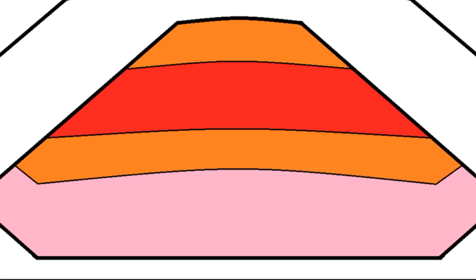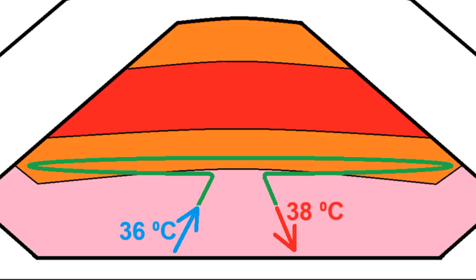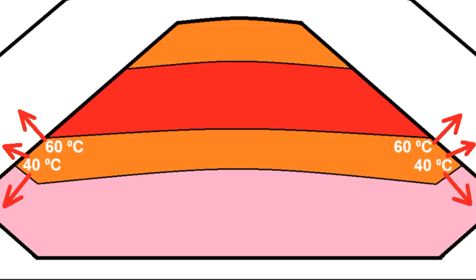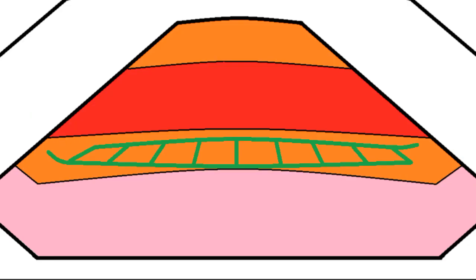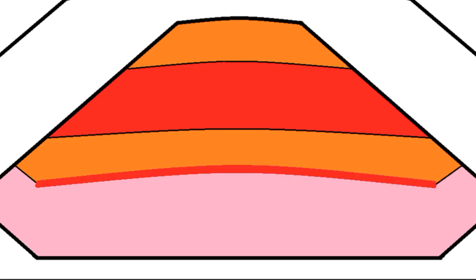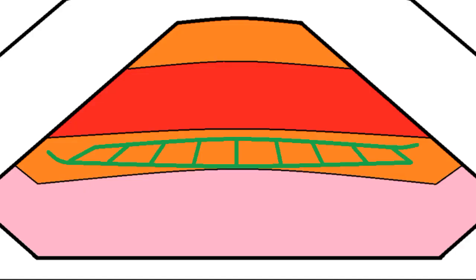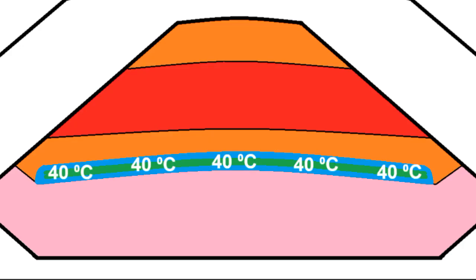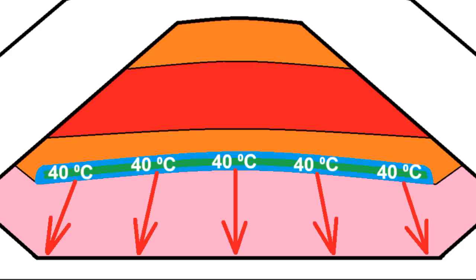In the lower part of the sand layer there is a ring of 30 meters of pipe. Circulation of home heating water through this pipe reduces the temperature of the hot sand in those places down to 40 or 60 degrees, reducing heat leaks in those directions several times. Additionally, the home heating system water circulates through a horizontal ladder of 80 meters of pipes installed 10 to 20 centimeters above the boundary between the sand and the granules. This reduces the sand temperature in those places down to 40 degrees, cutting heat leaks in those directions several times as well.